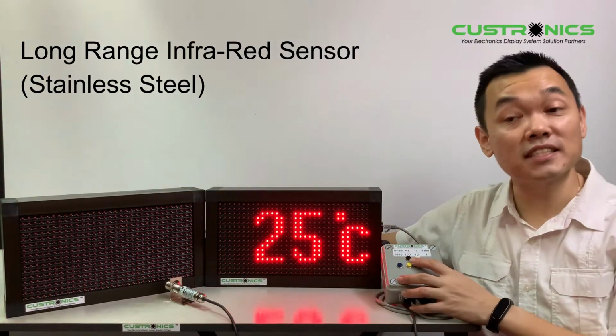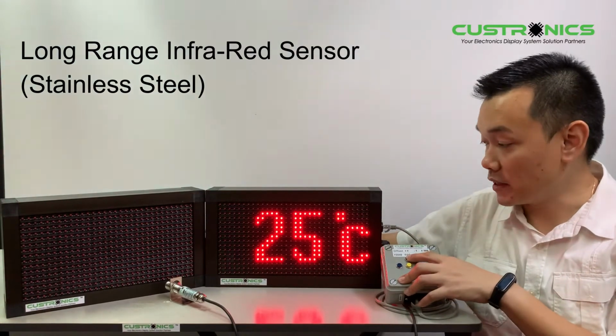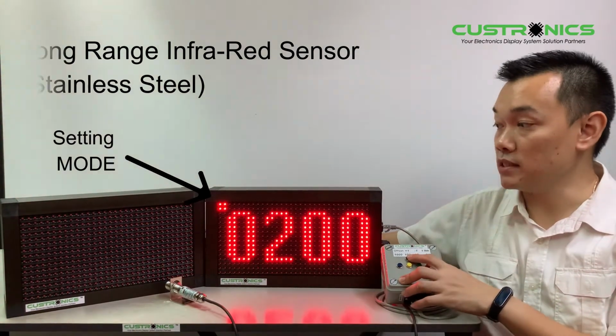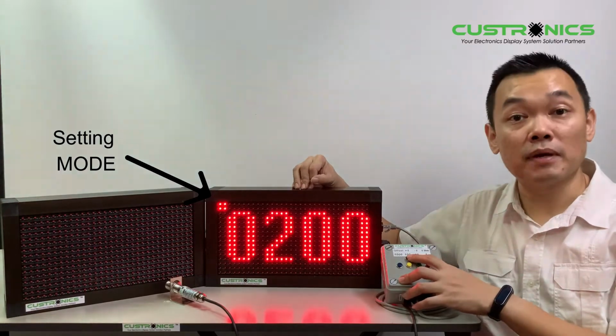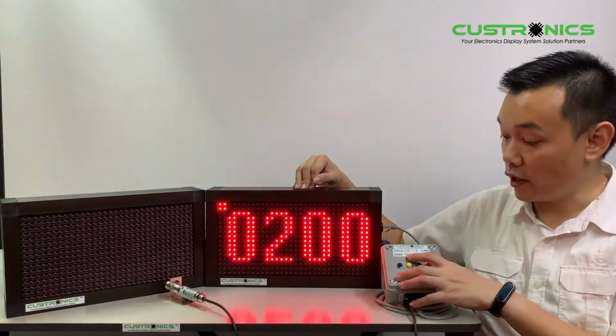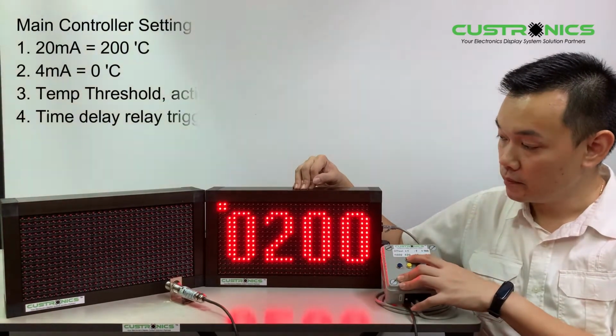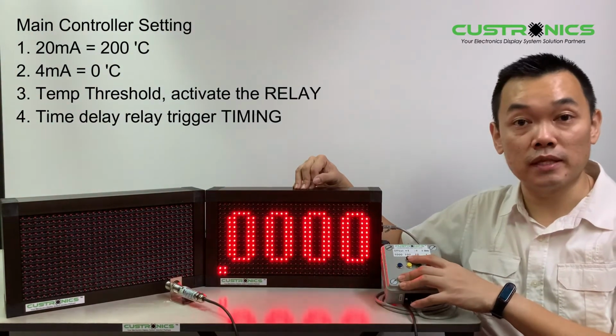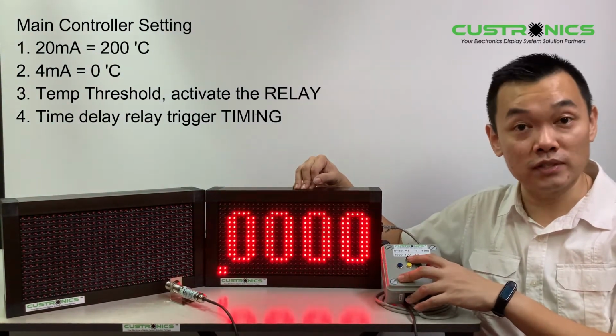Let's go to the setting. Press and hold the black color button to go to the setting. This is the 200 Celsius maximum, when 20 mA equals 200 Celsius. Press and hold again, this is the minimum temperature, meaning when 4 mA equals 0 Celsius.